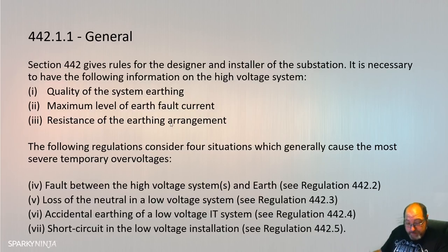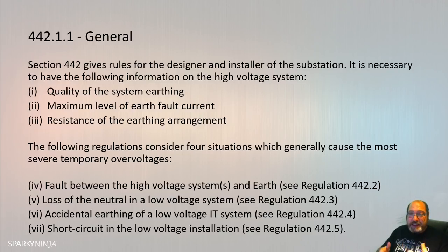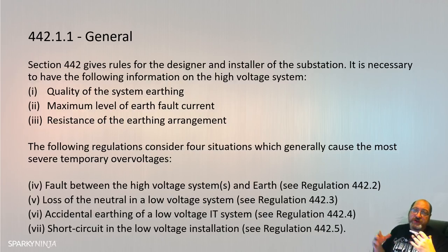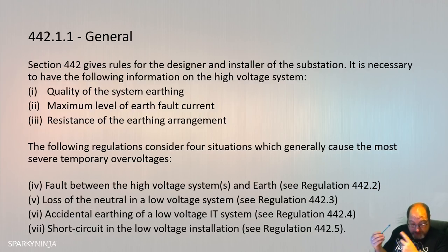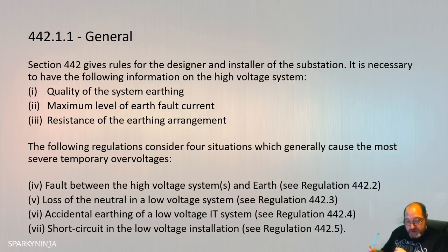Section 442.1.1: section 442 gives the rules for the designer and installer of a substation, so immediately for most of you that's going to be a concern. We'll just cover this for completeness. It is necessary to have the following information on the high voltage system: the quality of the system's earthing, maximum level of earth fault current, and the resistance of the earthing arrangement. The regulations consider four situations: fault between the high voltage system and earth, loss of neutral, accidental earthing of a low voltage IT system, and short circuit in the low voltage installation.